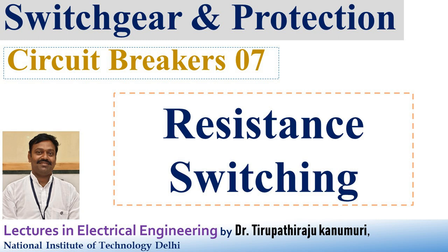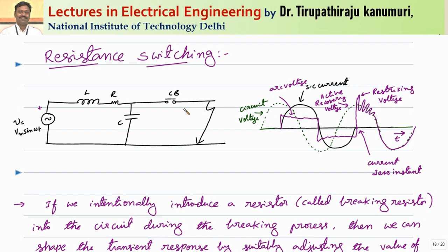Today we are going to discuss resistance switching of the circuit breaker. We have seen in the last class that whenever the circuit breaker contacts open at natural current zero, the arc will be extinguished. When the arc is extinguished, because most faults are inductive, the voltage should reach the active recovery voltage across the breaker contacts. But due to L and C circuits, high frequency oscillations are superimposed on the fundamental frequency component, which we term the restriking voltage, and this can go up to two times the rated value, causing the arc to restrike.